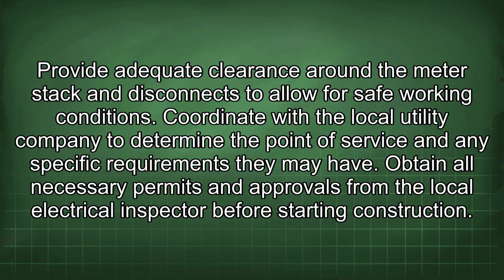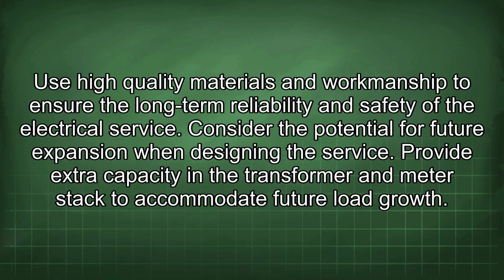Provide adequate clearance around the meter stack and disconnects to allow for safe working conditions. Coordinate with the local utility company to determine the point of service and any specific requirements they may have. Obtain all necessary permits and approvals from the local electrical inspector before starting construction. Use high-quality materials and workmanship to ensure the long-term reliability and safety of the electrical service.